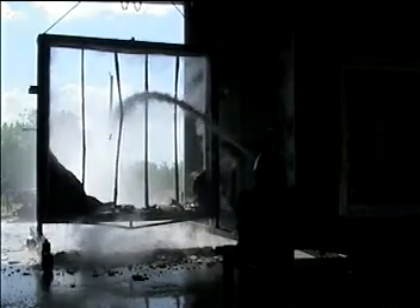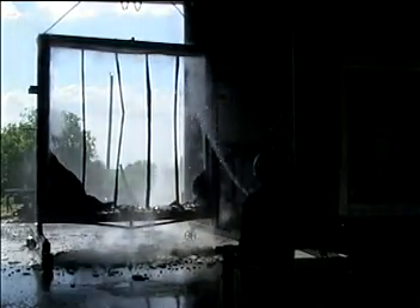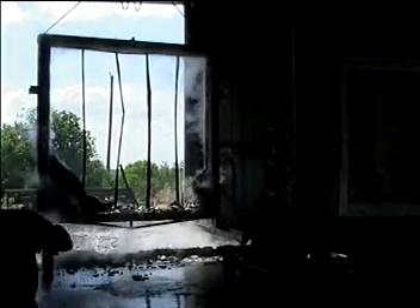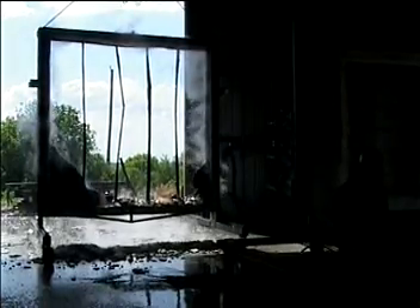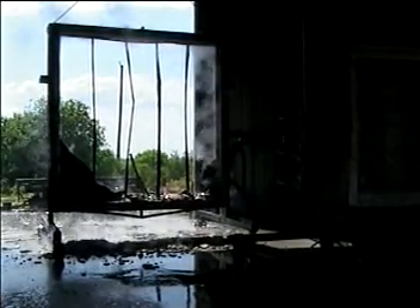This is a real-life situation — when a firefighter walks into a building, this is what's burning: two-hour fire-rated sheetrock walls supposed to protect the occupants. This will not protect occupants, will not protect property, and will not give you the time to get out of a burning building. Gypsum can be retested for one hour, and if it passes the hose stream test at one hour they give it a two-hour rated assembly — but that doesn't really reflect what happens in an actual fire condition. We don't get a second chance in fires.